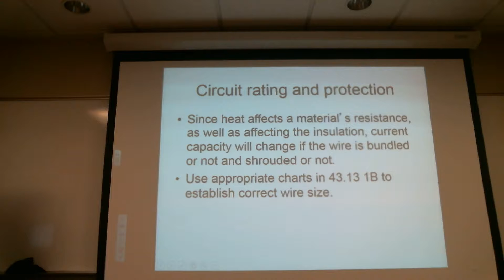So basically, if I've got one circuit that I'm going to have circuit protection on, I've got that circuit breaker there. I'm going to add up all the users on that circuit breaker and make sure they don't exceed the total output for that circuit breaker. Now, it may well be I don't necessarily want a bunch of stuff on the same circuit breaker. I really wouldn't want my nav lights and my fuel pump on the same circuit breaker. It just doesn't logically make a lot of sense.